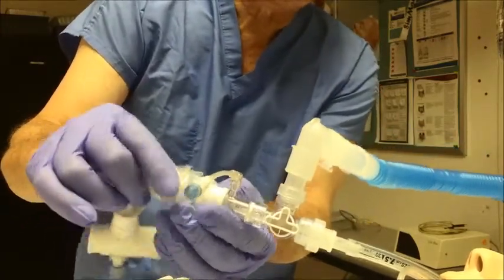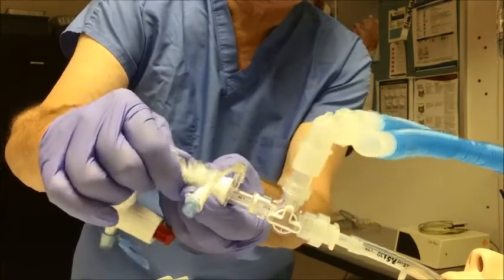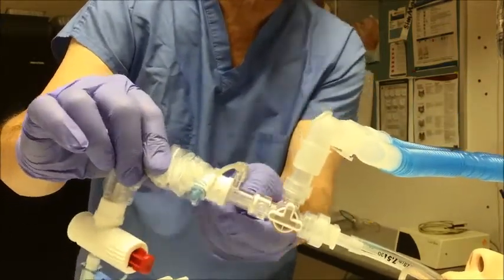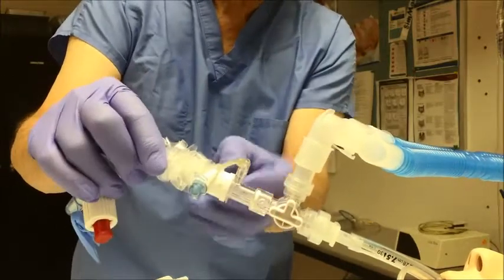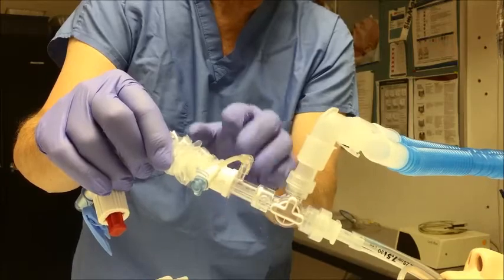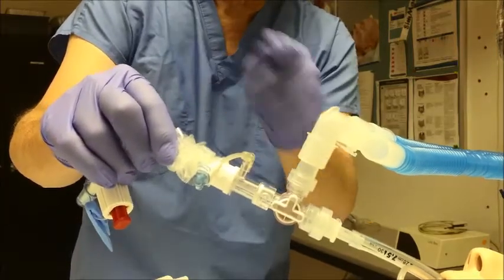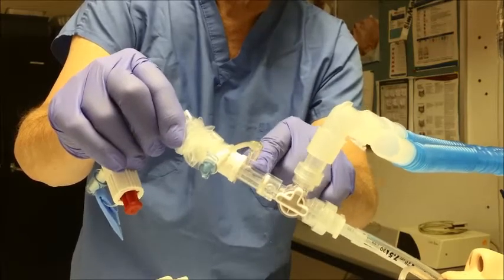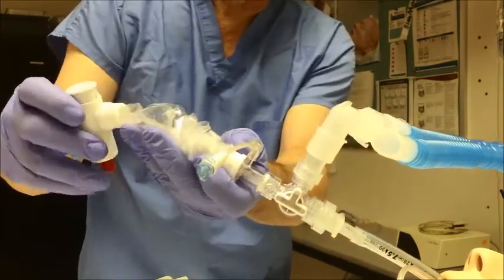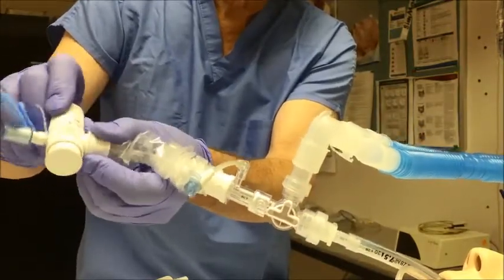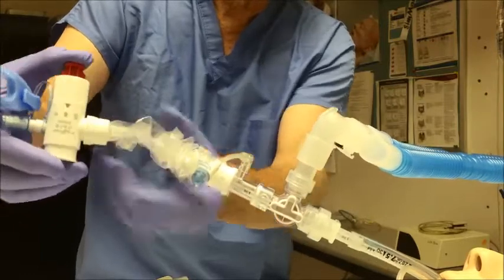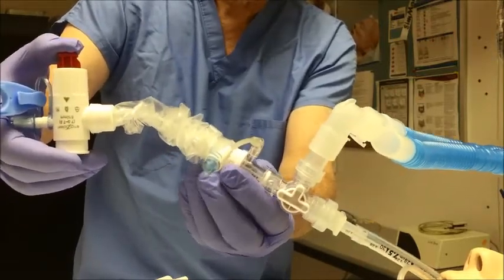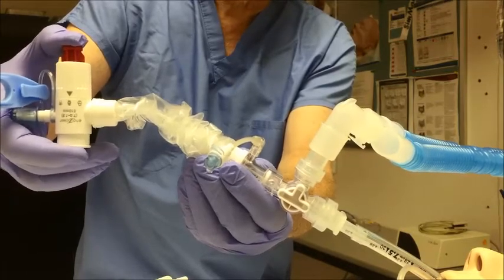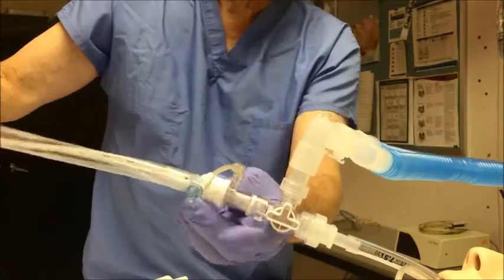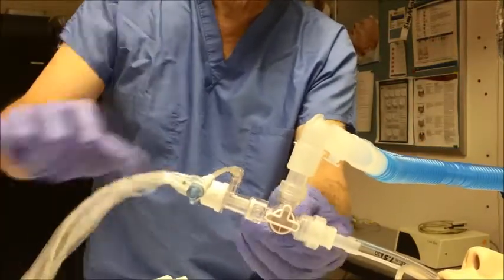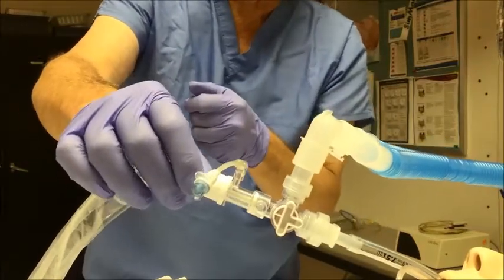At that time, we also look in the cleaning garage window and are able to see a centimeter marking, which in this case says 38. What can subsequently be done is that every other time this device is used, the catheter can be inserted up to the 38 in this window and know that it's in the correct position distally. Once that's been done, the control is turned to wiper, and with a patient inspiration or a ventilator inspiration, the wiper is deployed and pulled back into the cleaning garage, and the stopcock is closed.